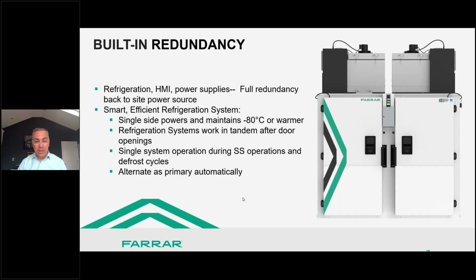But we also have 2 dual human-machine interfaces, or HMIs, that each can control the system when the other is offline. So you have 2 normally. You can control either the one on the left side of the door or the right side, doesn't matter. And if one goes down, whichever one is left will control the whole system.